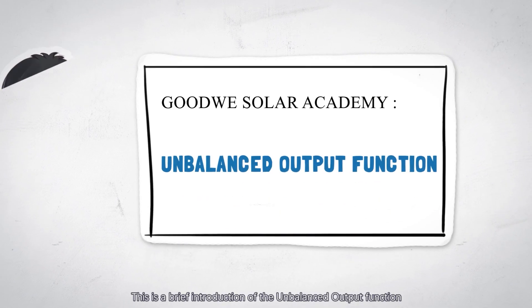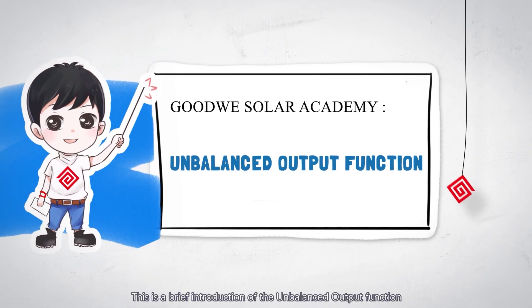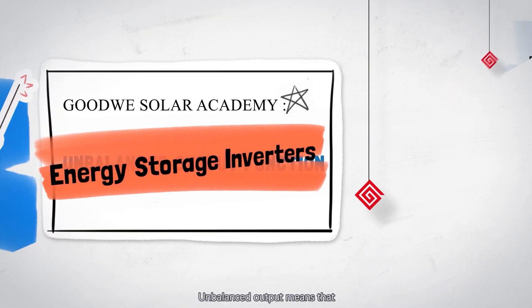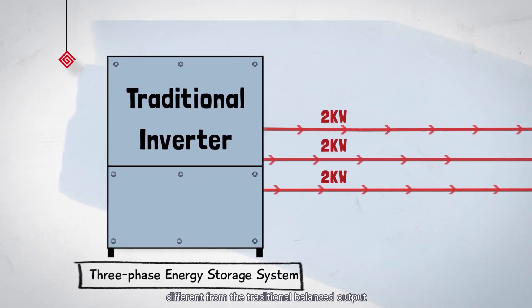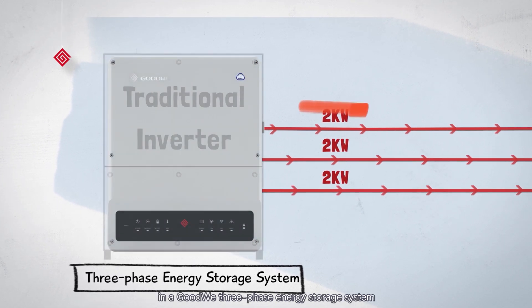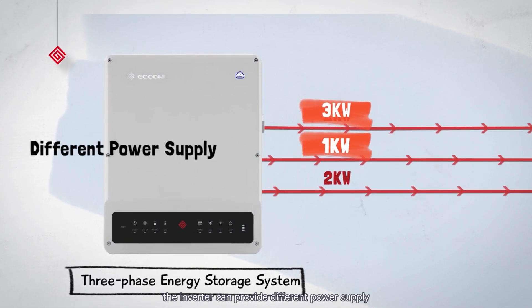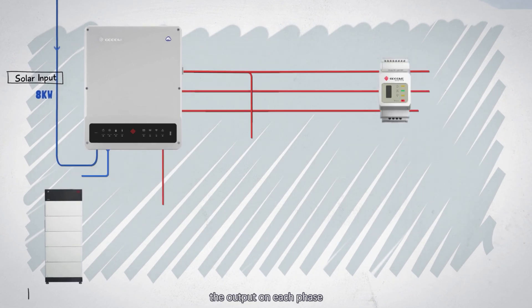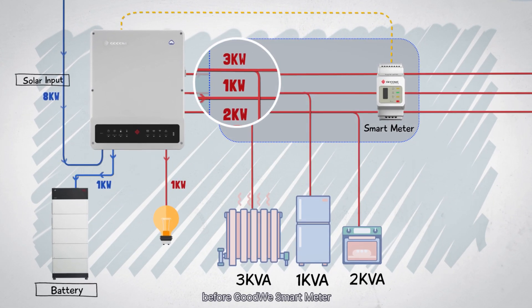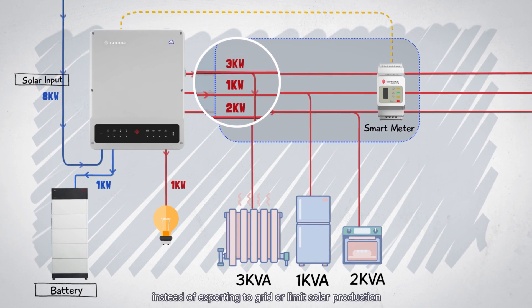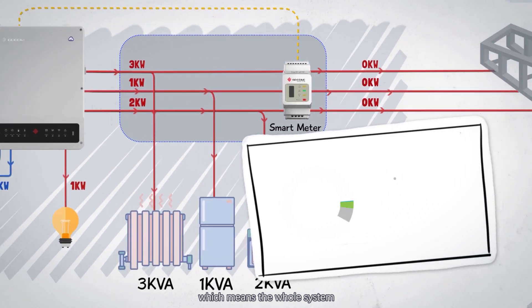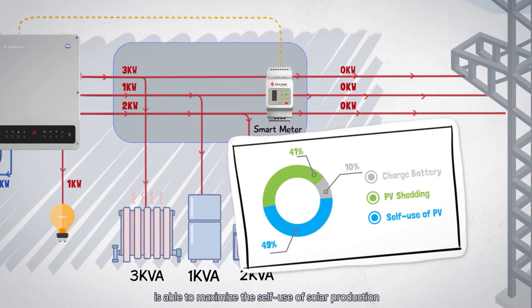This is a brief introduction of the unbalanced output function of Goodwe energy storage inverters. Unbalanced output means that, different from traditional balanced output, in a Goodwe three-phase energy storage system the inverter can provide different power supply on three phases at the same time. Each phase can share power with other phases via the Goodwe smart meter, instead of exporting to the grid or limiting solar production, maximizing the self-use of solar production.